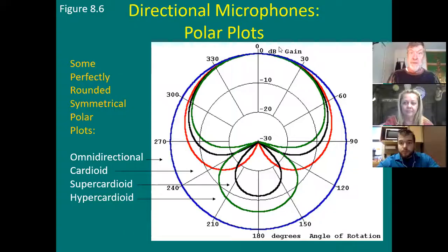Okay, but remember now, I'm wearing the hearing aid on the side of my head. So the round polar plots that I just showed you in the picture aren't going to happen. They're not as good. So do you know what? A D mic actually doesn't increase the signal to noise by 5 dB. And the directional index isn't as good as 5.